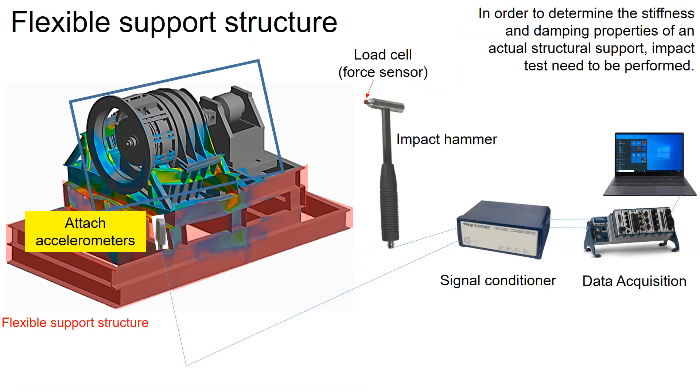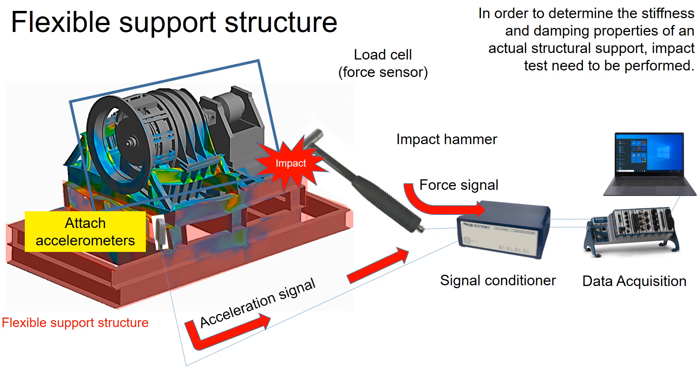To determine the stiffness and damping properties of actual structural support, we need to perform an impact test. During the test, force signal from the hammer and acceleration signal from the accelerometers are transferred to the data acquisition.